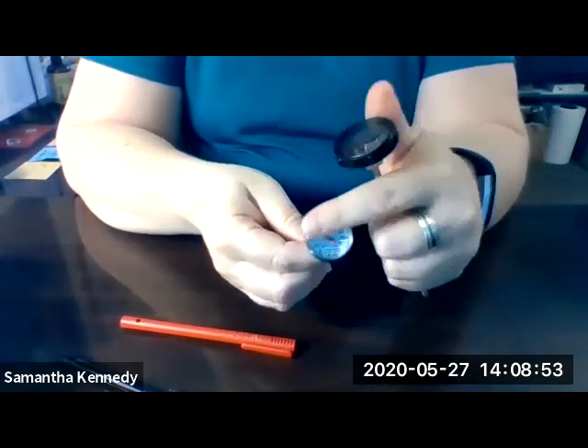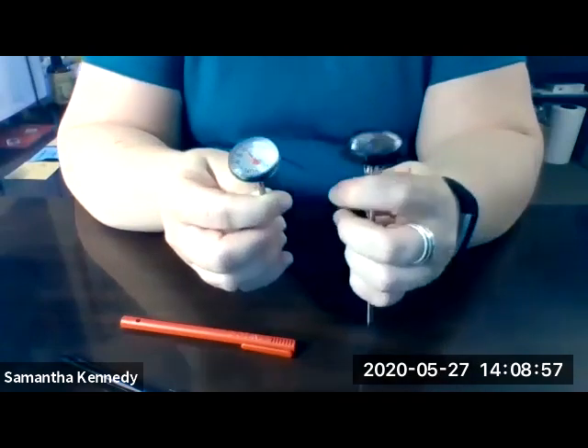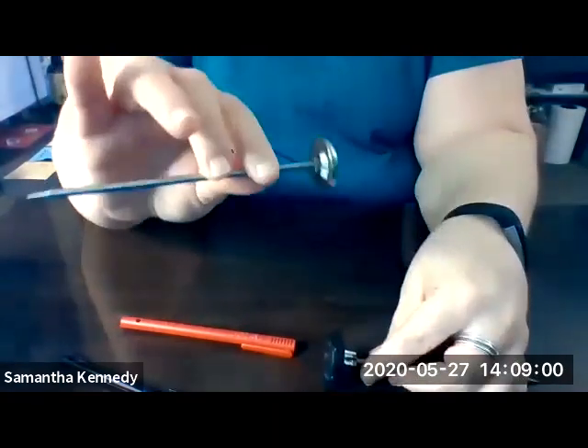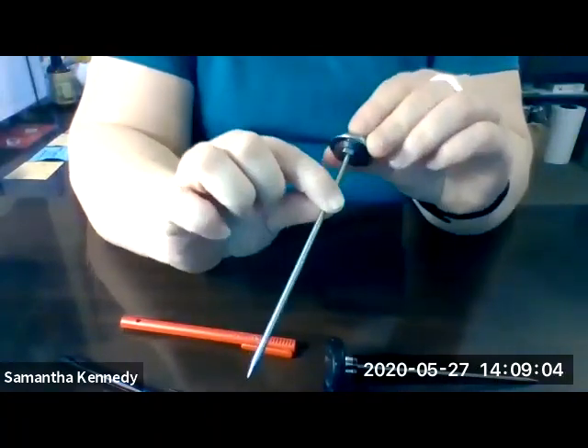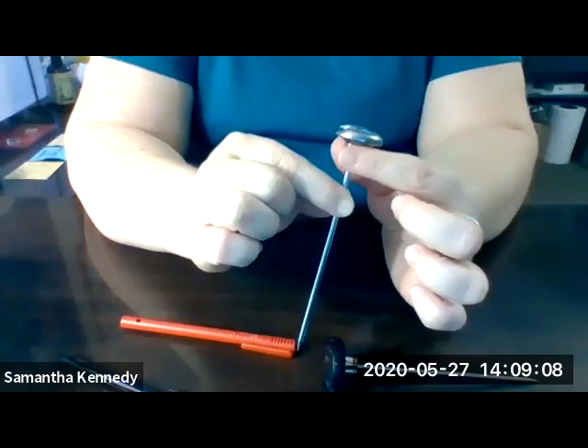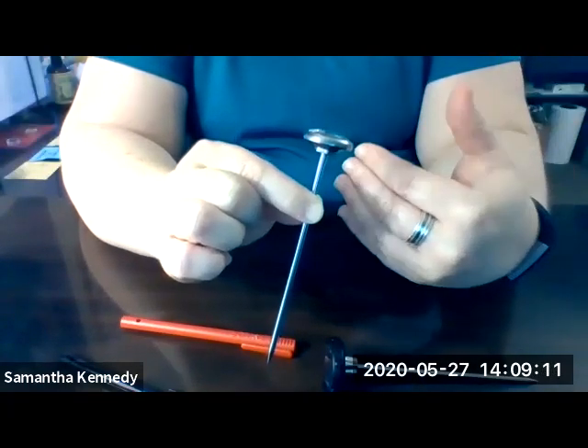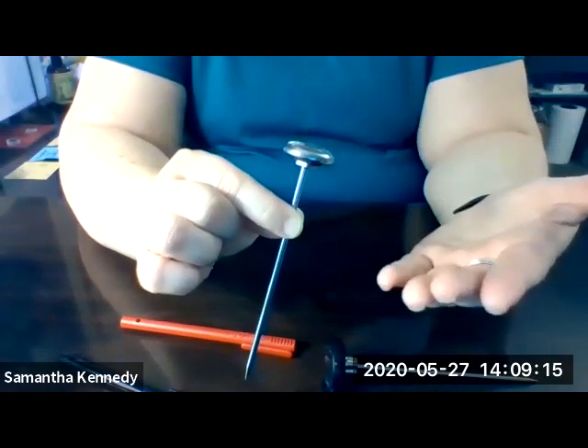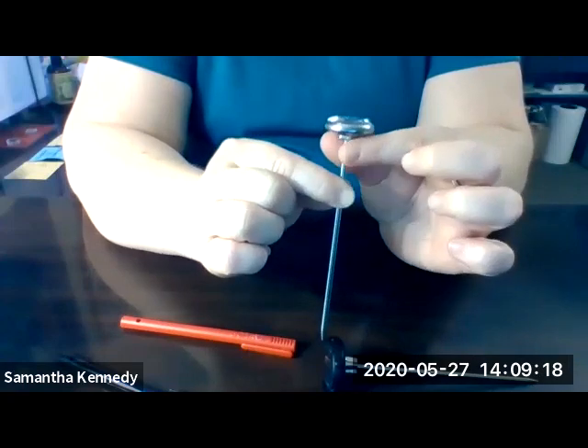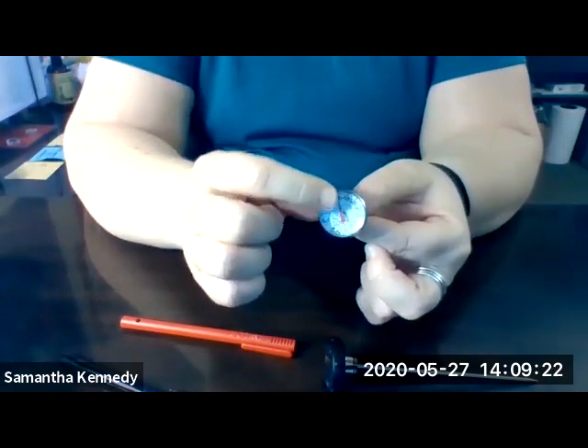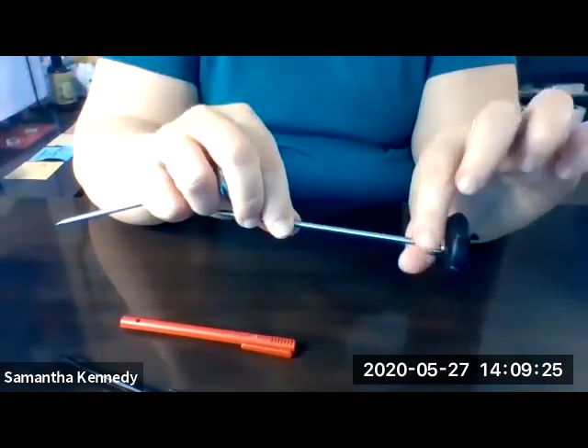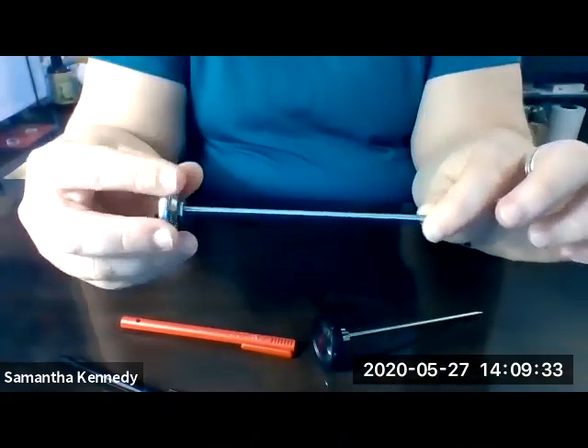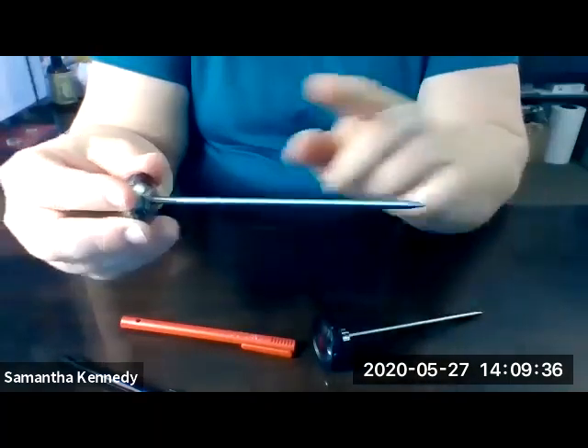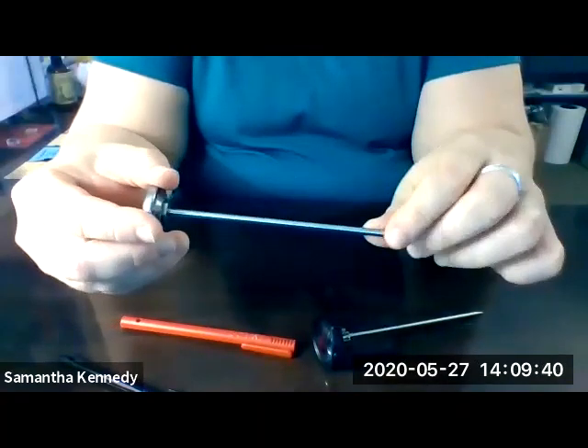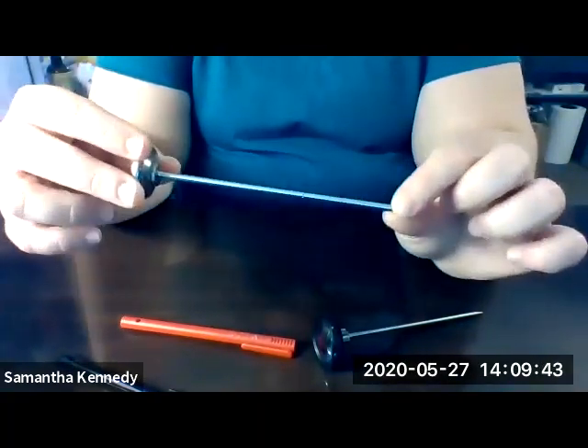So you have, again, the head or the face of the dial here. And then you can see underneath on this one the calibration nut. It's got a little nut underneath it, and it's called the calibration nut because when you're calibrating your thermometer, meaning you're testing to make sure that it's accurately measuring temperature, this is what you would turn to get the needle to point to the right temperature. This one just has a calibration nut too, it's just a different shape. Then you have the stem of the thermometer. You can see it's made out of two different kinds of metal. You can't really tell the difference by looking at it, but that's why it's called bimetallic. It's made out of two different kinds of metal.